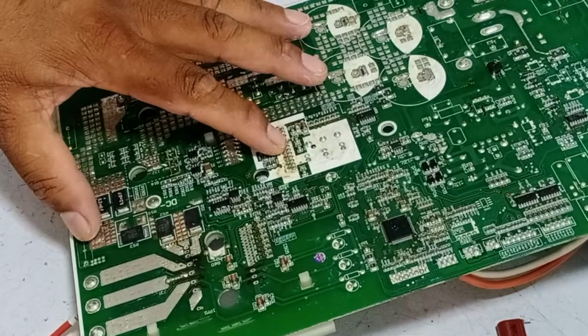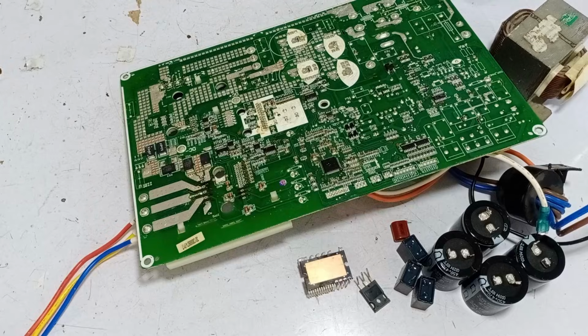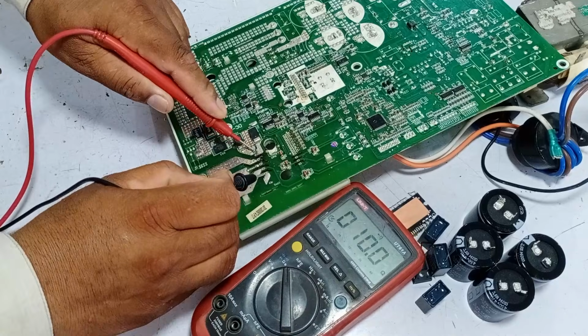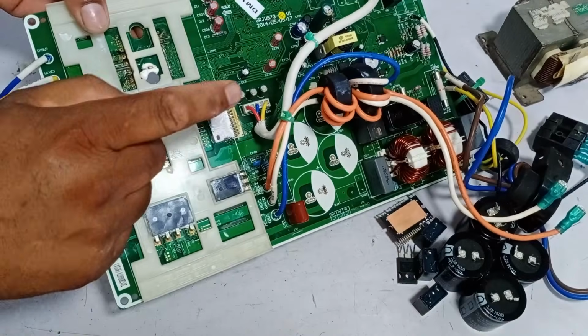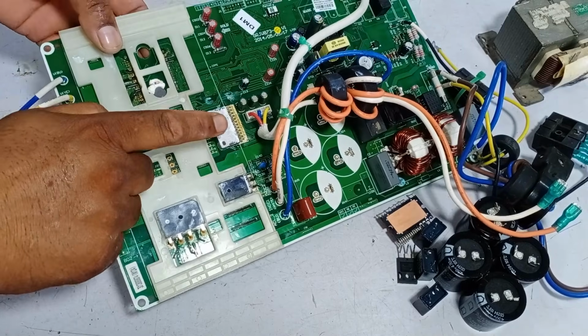That's why I'm thinking of removing the fan IPM. The compressor drive's IPM pad is still showing a short circuit - you can hear the beep sound from the multimeter. So let's remove the fan motor's IPM and check it on the circuit board.